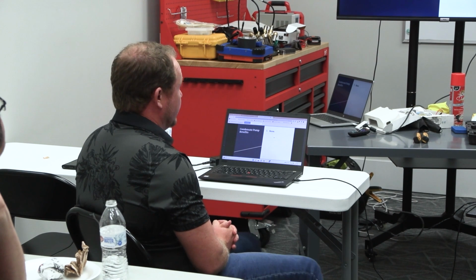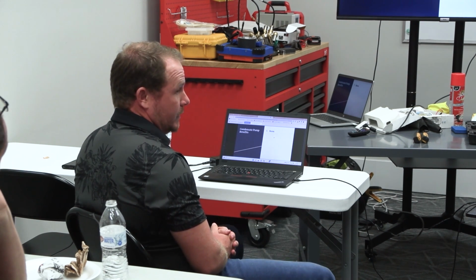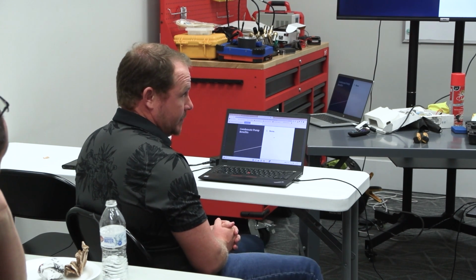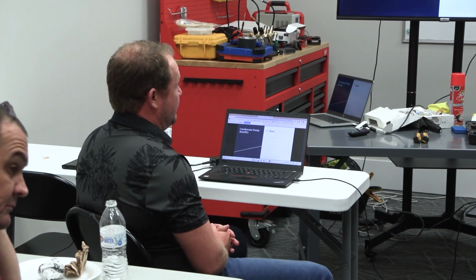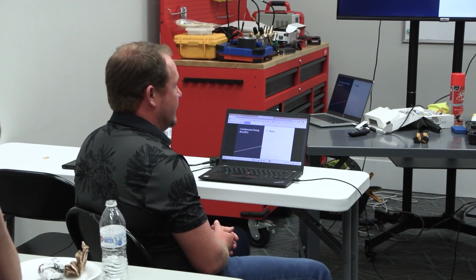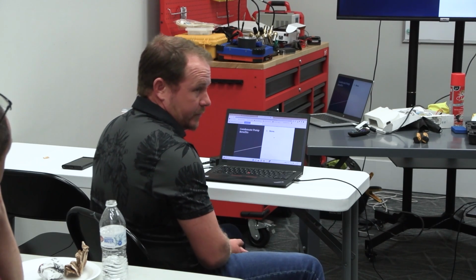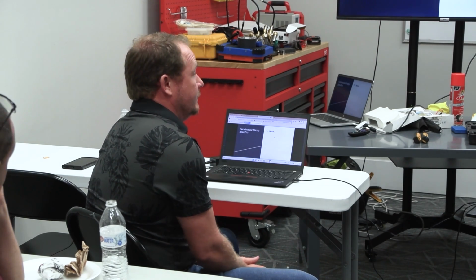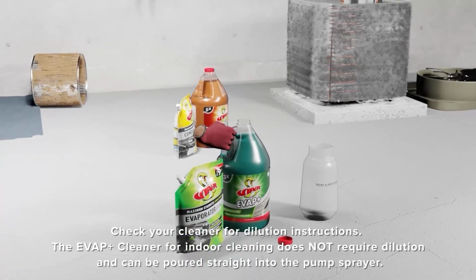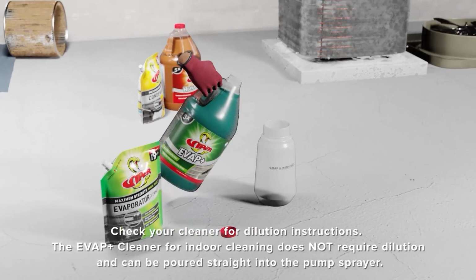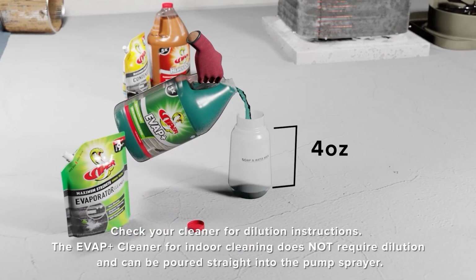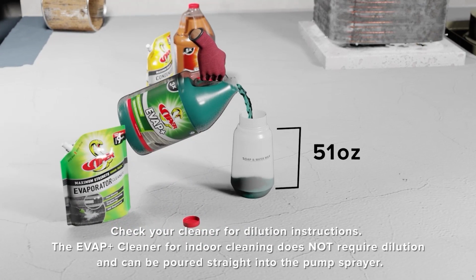And another thing is, don't run chemicals through a condensate pump. Don't run hardly any chemicals through a condensate pump. It's usually going to destroy them, except the very most mild. And even when you do, make sure you run fresh water through to clear them out. So like for us, using the EVAP Plus properly diluted, you could run some of that through there, but I wouldn't even leave that in the reservoir. It's just that they're very sensitive to cleaners. We'll get a little deeper into the actual maintenance side of things coming up here.